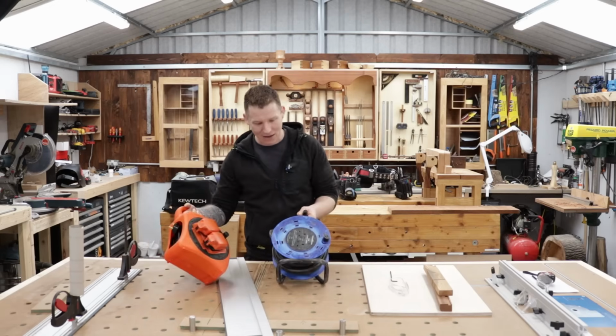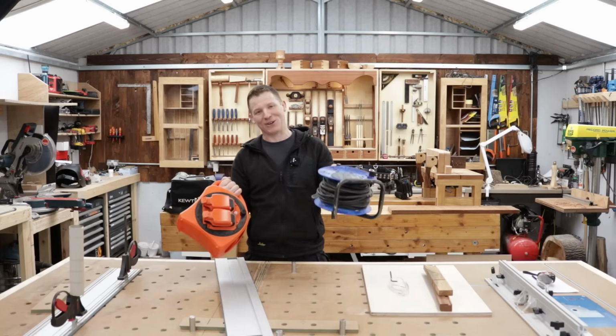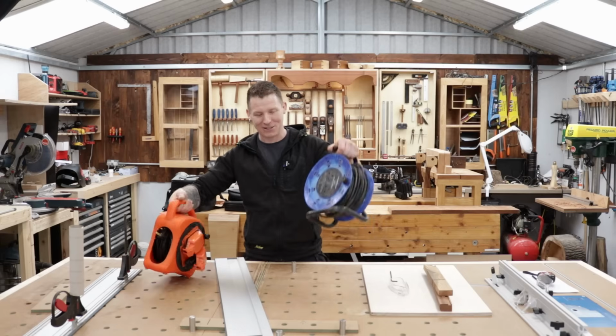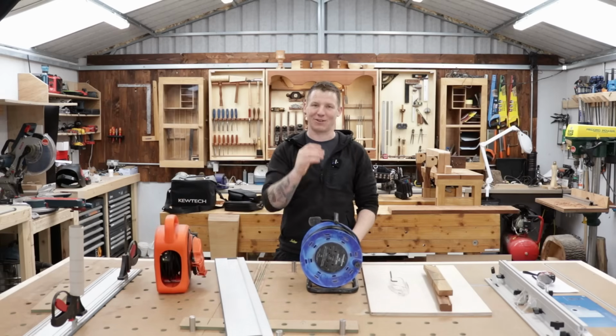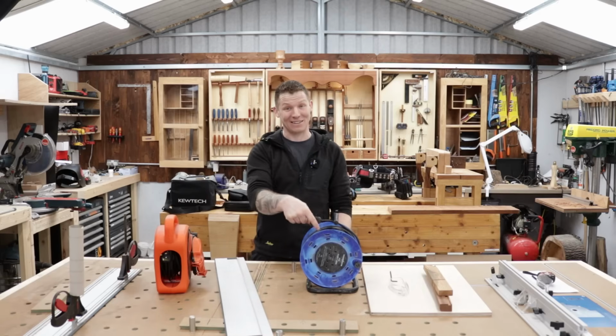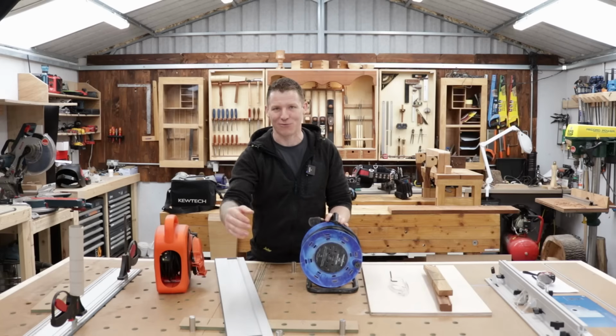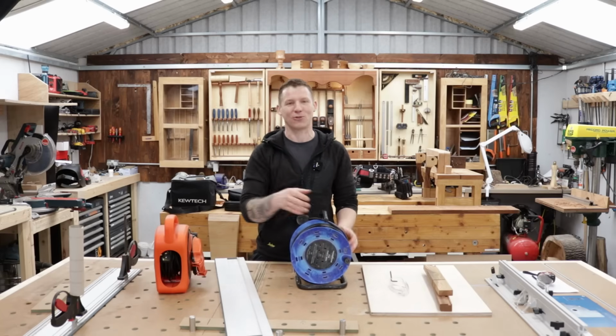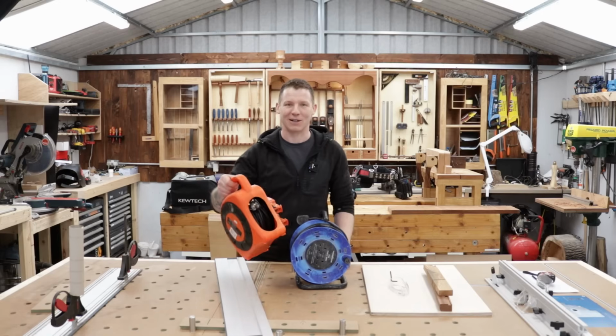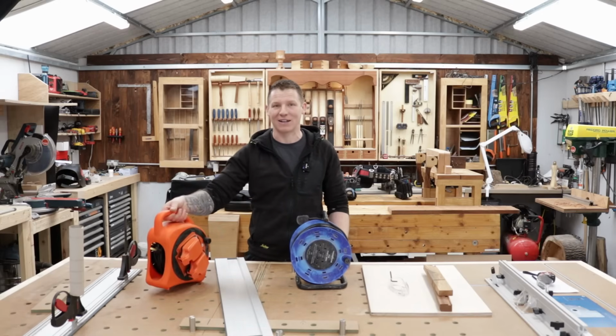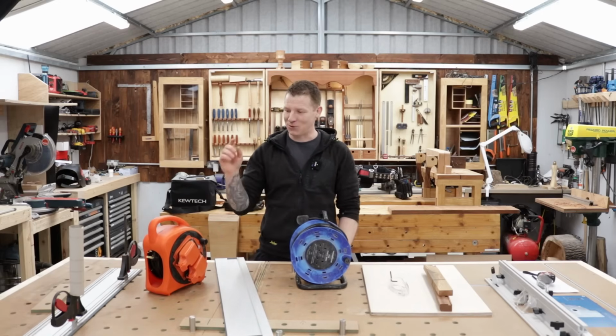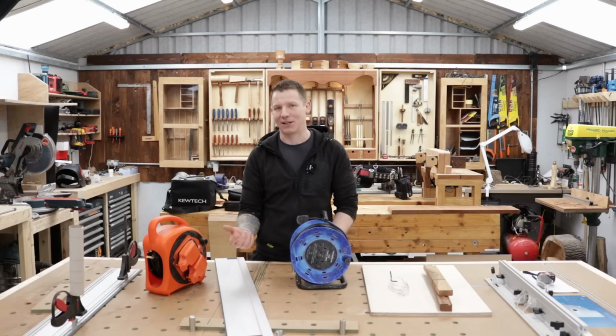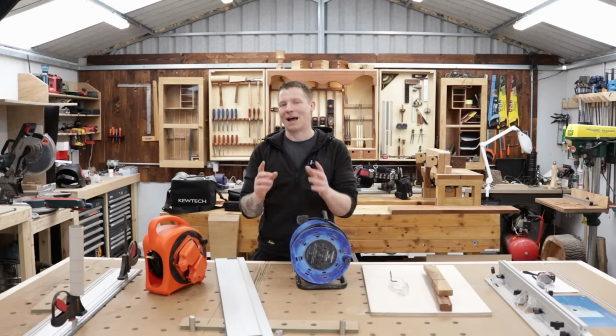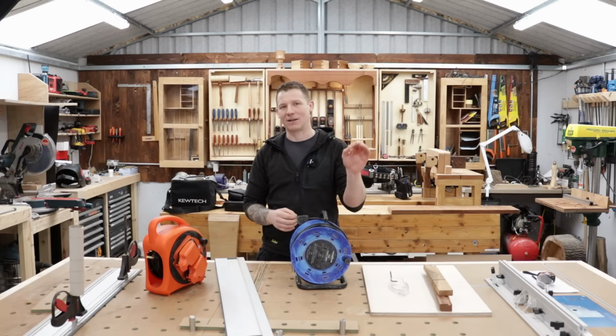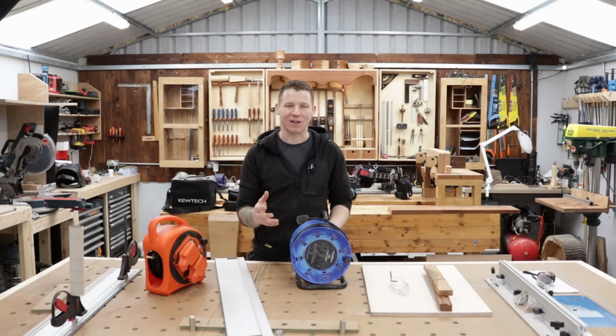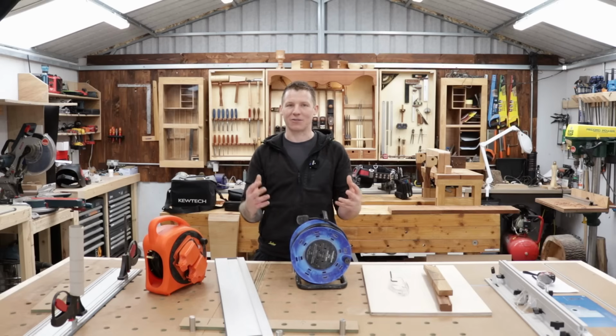Another thing to think about is never ever plug another extension lead into another extension lead. Again, you could be plugged into the last socket on a circuit. You've just added 20 meters. If I was to plug this extension lead into this extension lead, say I only wanted to go an extra meter further and I was just a meter short, so I thought, I know what I'll do, I'll go and grab my other extension lead, I'll plug that into it. Well, you've just added another 20 meters to that circuit now. What happens if you get a damaged cable or a damaged tool that you plug in there? If you get a short circuit, what will happen is it won't blow out the breaker. It'll turn that whole circuit into a heating coil, and those cables will glow red hot, and that breaker will not go out.